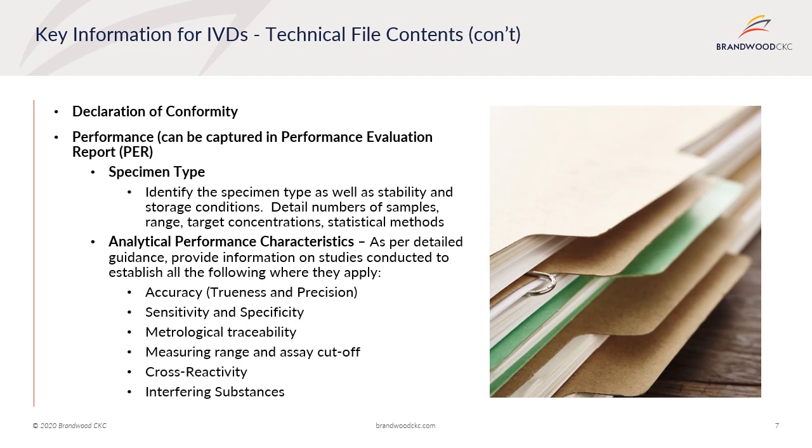And because it's the most important piece of the IVD, especially as it relates to regulatory review and what the regulators are looking for. And that's the performance. Now, typically, these are captured in what is called the performance evaluation report, although that may change depending on jurisdiction. It may be the summary of safety and effectiveness. It may be a summary of analytical performance. But in general, I'm going to refer to it as the performance evaluation report.